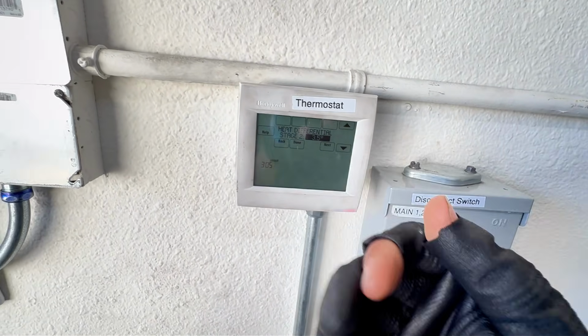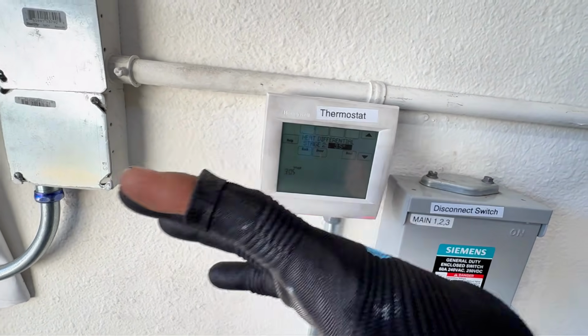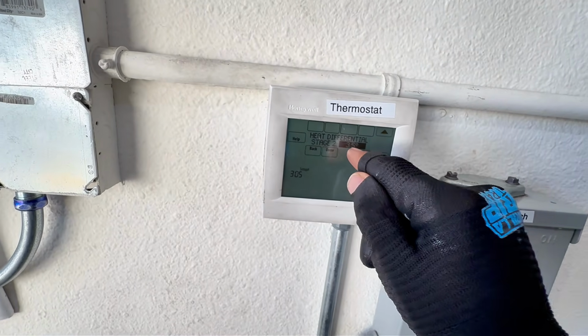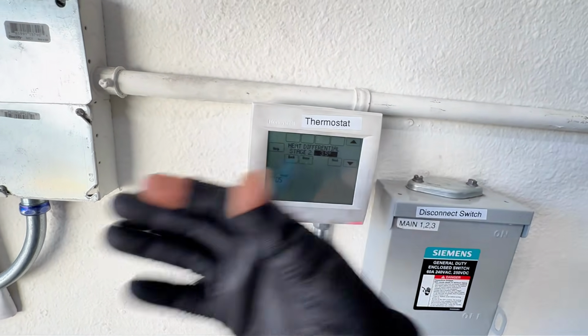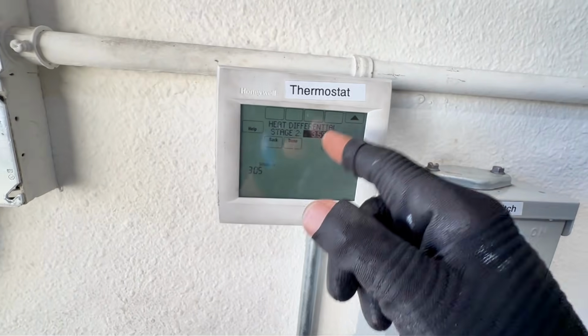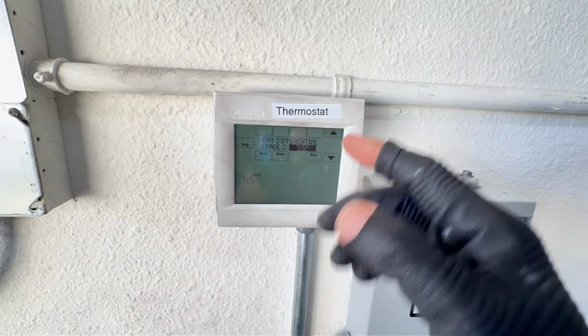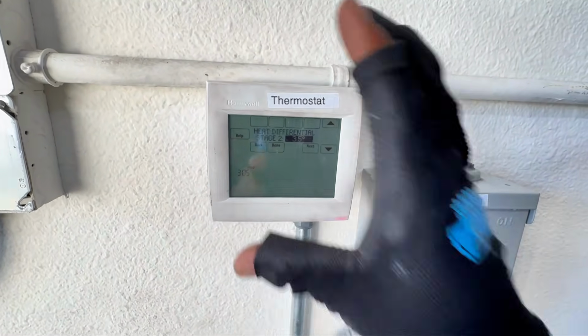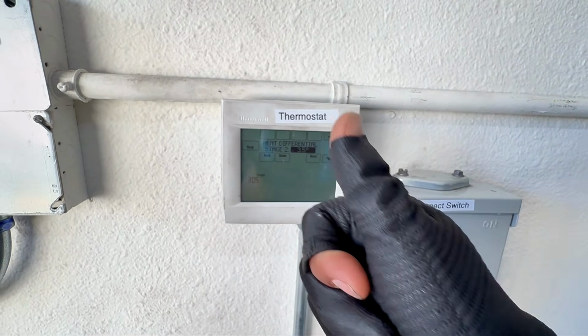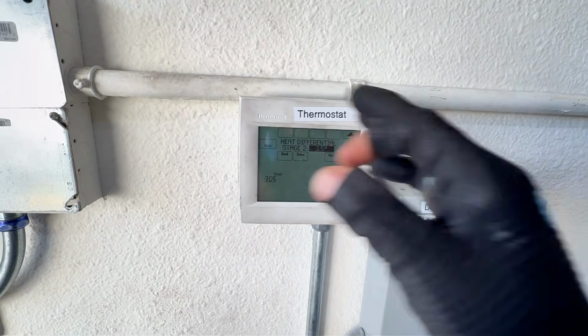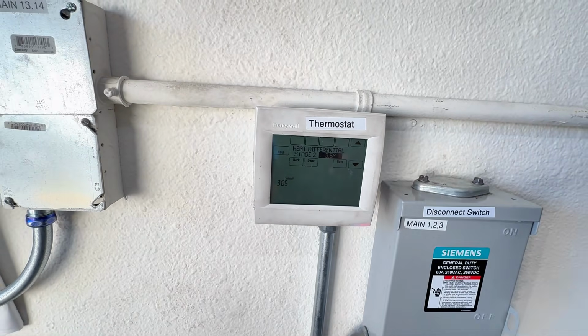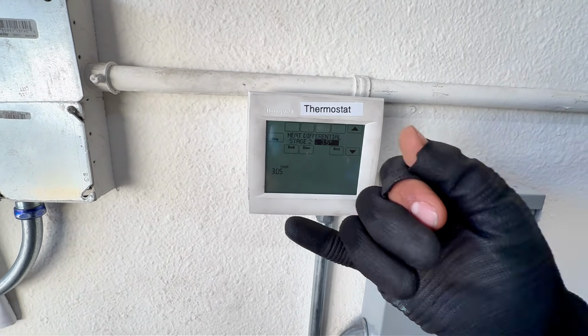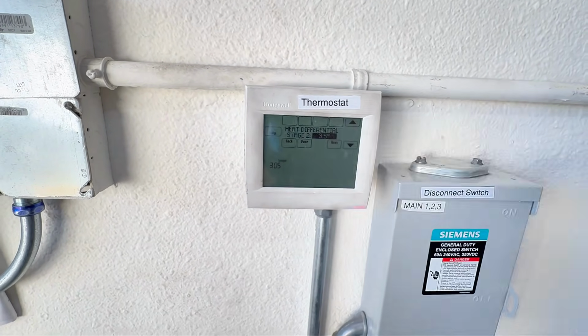It's the same concept. If your ambient temperature is further away from the set point, if it exceeds that 3.5 and it's 5 degrees colder, it's going to do stage 2. So you can set the set point or choose comfort. But it's important to read the manual first to understand that it can do stage 2, and to set it up so that it actually turns the system on in stage 2 heating or stage 2 cooling.